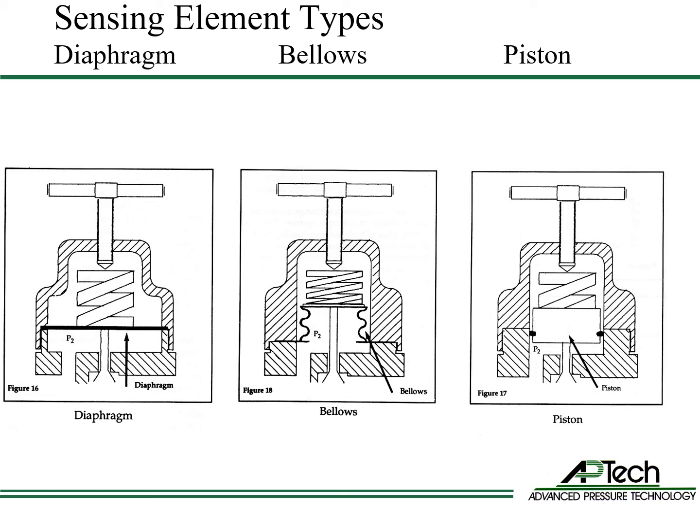Pistons have greater stroke, are less expensive, and can handle higher pressures. For example, the APTech KT10 is used up to pressures of 10,000 psi. However, pistons have dynamic o-ring seals to atmosphere, which generate particles and don't have the leak integrity of metal to metal seals.